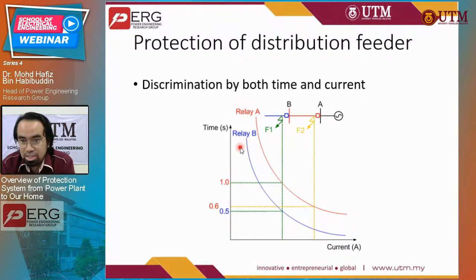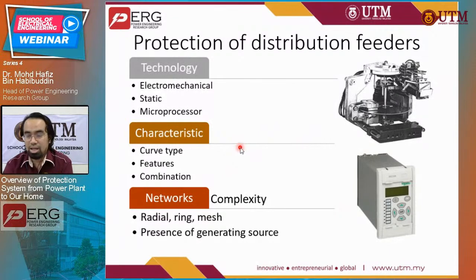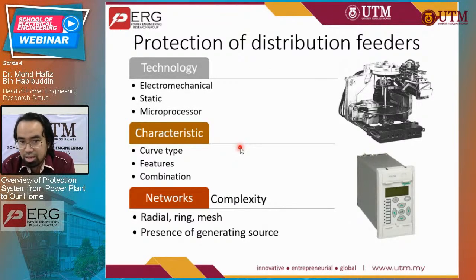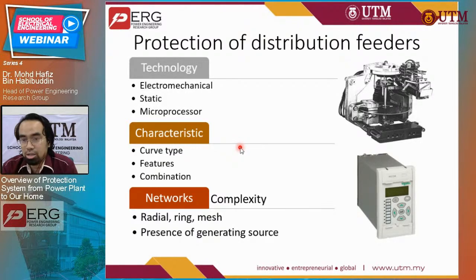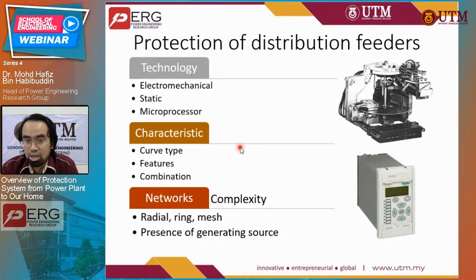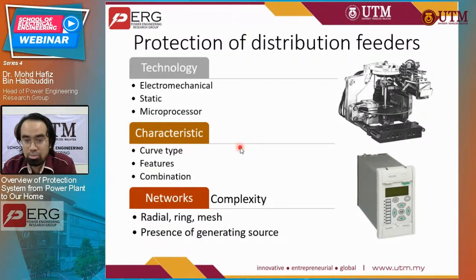This kind of coordination is easy with a simple radial system, but if the network gets complicated — for example, instead of radial you have a ring or mesh system — coordination becomes more elaborate and tedious. You might also have generating sources at the distribution feeders such as distributed generation, photovoltaic systems, or wind farms. In order to handle this, you need to utilize advanced tools — optimization tools and special computation tools for the relay settings. It cannot be done manually — or it can, but it would be very messy.